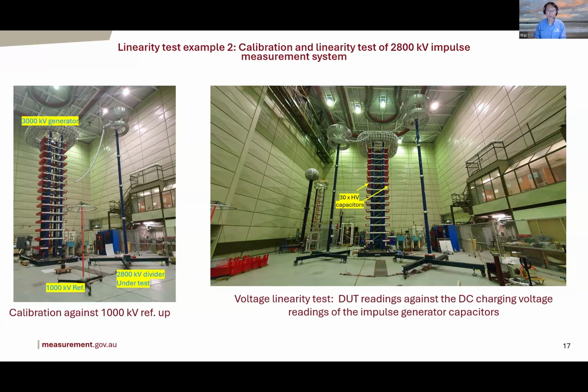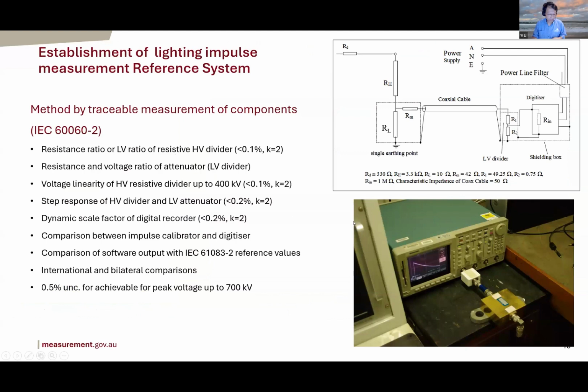So that's another example. Okay, so we have calibration devices. We can do the linearity test to cover the operating voltage of the measurement system. But how do you establish the traceability of your reference? Now we'll talk about a few examples. So first of all, this is a lightning impulse. A lightning impulse reference normally consists of a non-inductive resistive divider and a low voltage divider and a digitizer or digital oscilloscope, right?